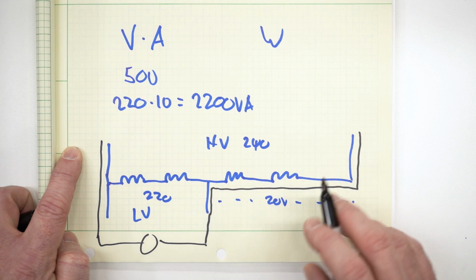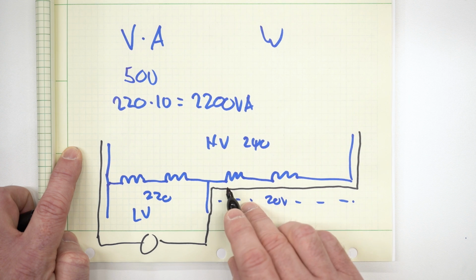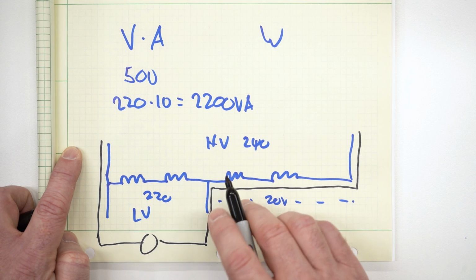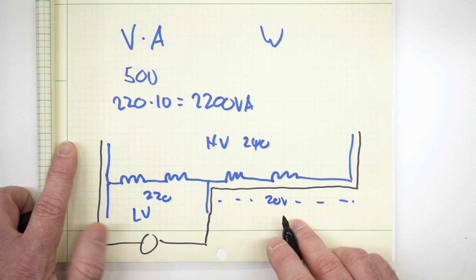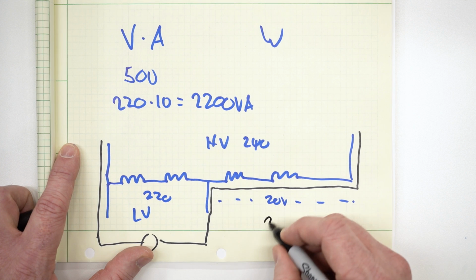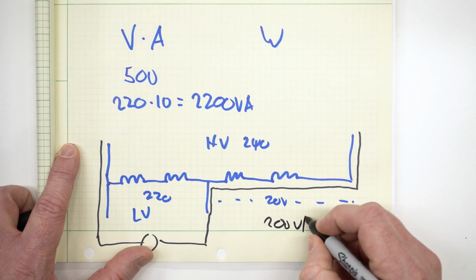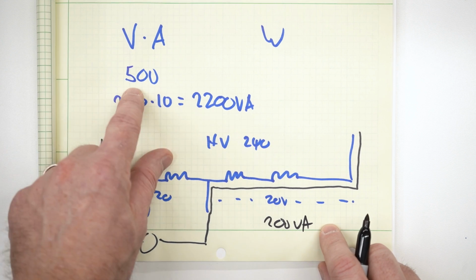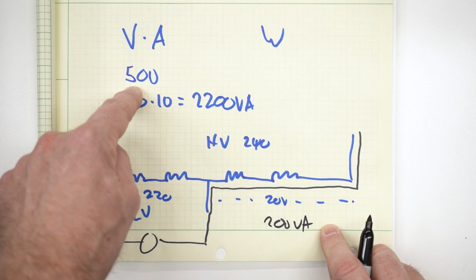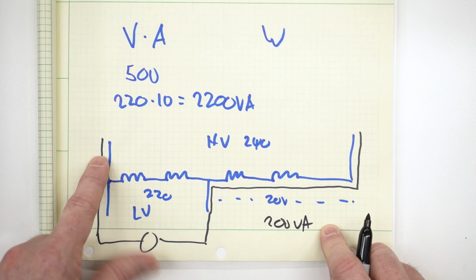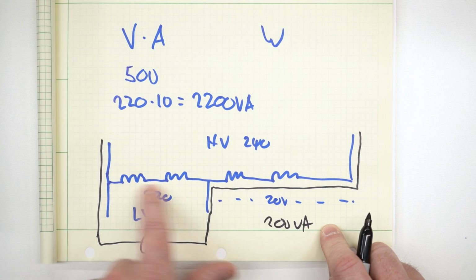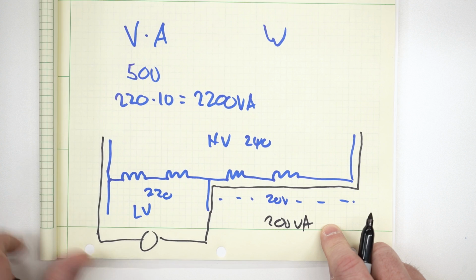As a result, we need a transformer that can handle the current here. If this is 20 volts at 10 amps, that's 200 VA, which means our 500 VA transformer will be plenty to handle that current flow, because we're not having to measure this since that's not where the current is flowing.